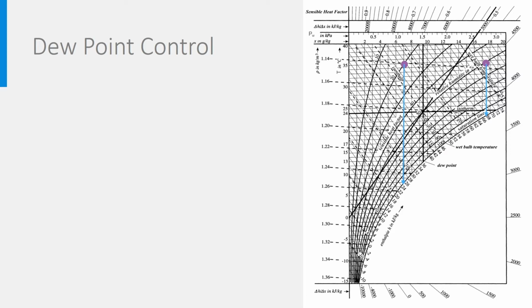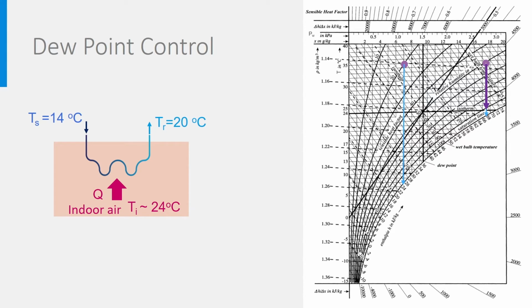Maybe you ask yourself now, what is the point? Why would we cool down to such low temperatures? Even 23 degrees in the first case is more than enough. Well, that has to do with heat exchangers and the needed temperature difference to achieve heat exchange. We need to keep the room air at 24 degrees. Therefore, TR, the water return temperature, must be below this temperature, let's say no more than 20 degrees.